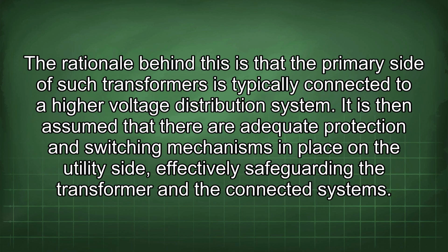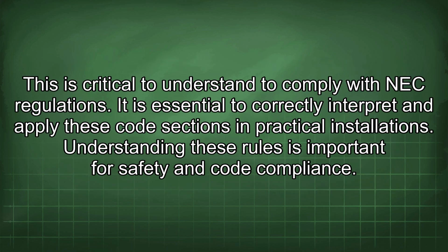The rationale behind this is that the primary side of such transformers is typically connected to a higher voltage distribution system. It is then assumed that there are adequate protection and switching mechanisms in place on the utility side, effectively safeguarding the transformer and the connected systems. This is critical to understand to comply with NEC regulations. It is essential to correctly interpret and apply these code sections in practical installations. Understanding these rules is important for safety and code compliance.